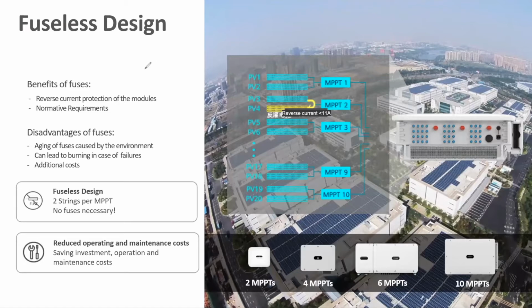Another nice feature is that we have a fuseless design, so it's not mandatory to use fuses on the DC side. This is thanks to the fact that the MPPTs, which can handle 2 strings, can tolerate the reverse current, for example. So it is not mandatory to use them. Some disadvantages of using fuses is that aging is very prevalent because of the environment. And because of failures, it can lead to fires, for example. And of course, it's an additional cost. Thanks to our design, this is not necessary to use.